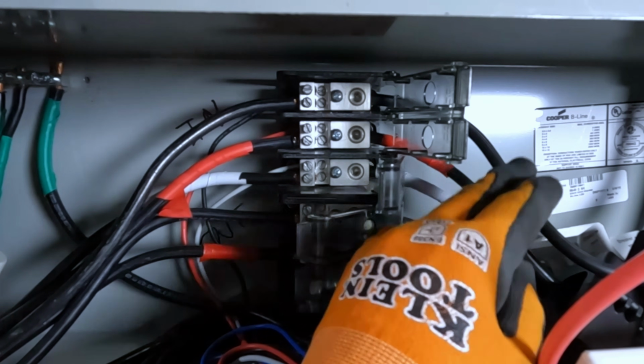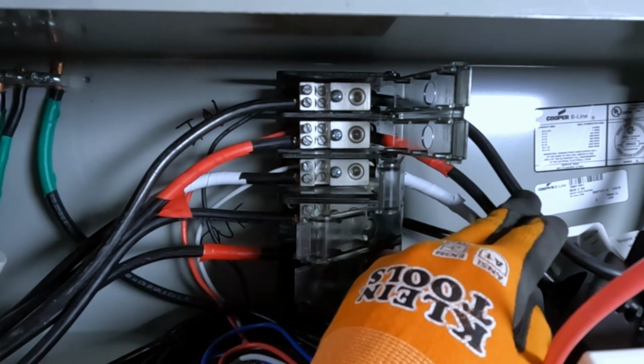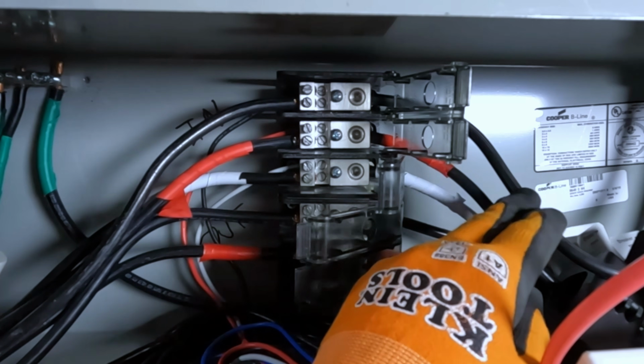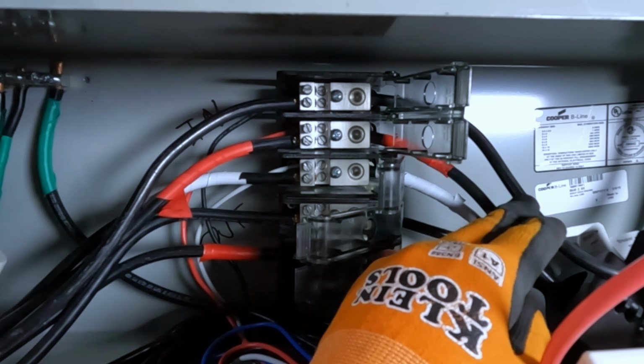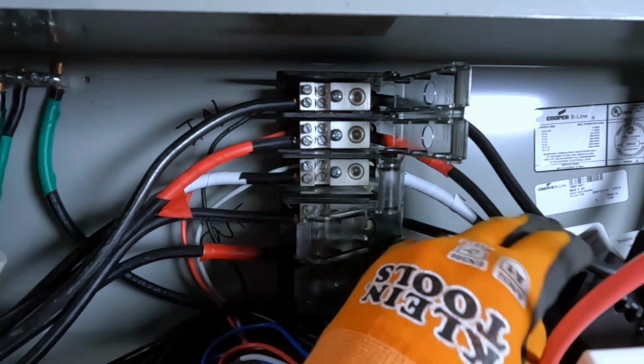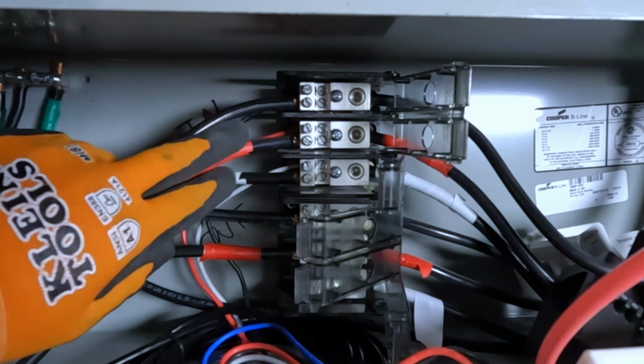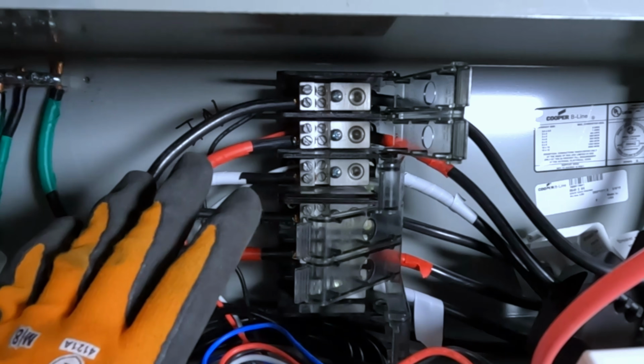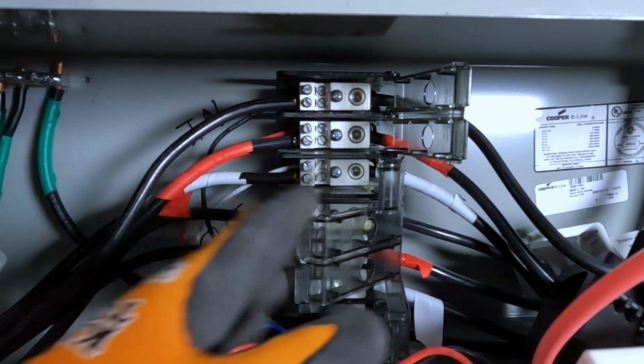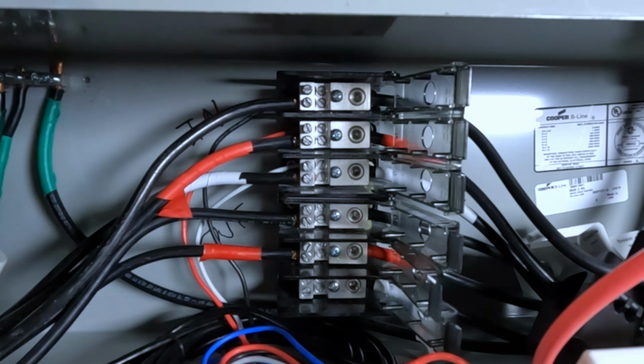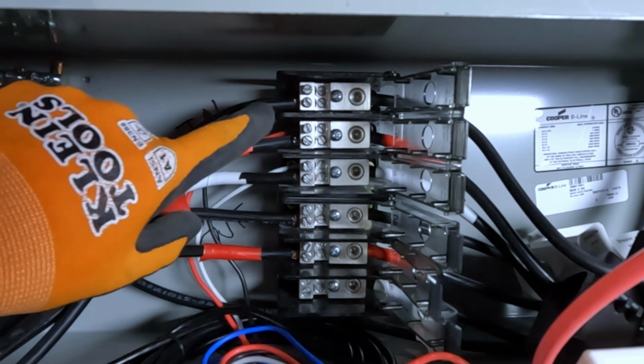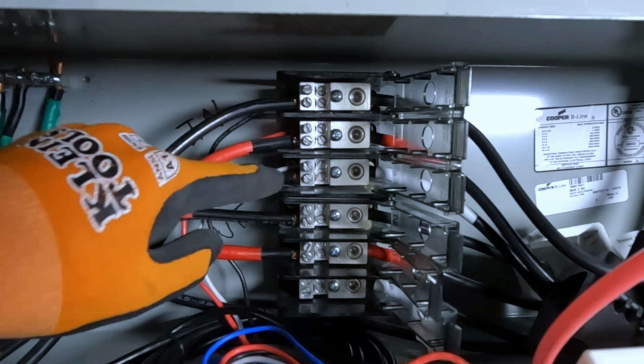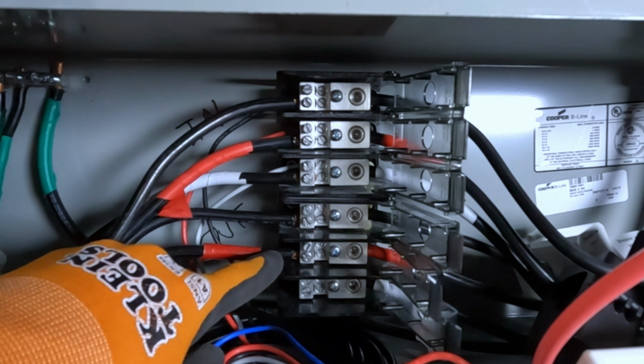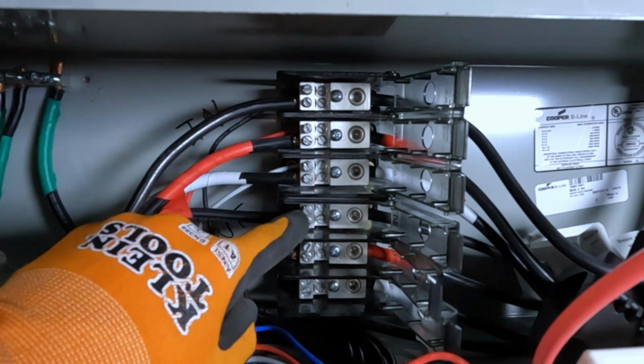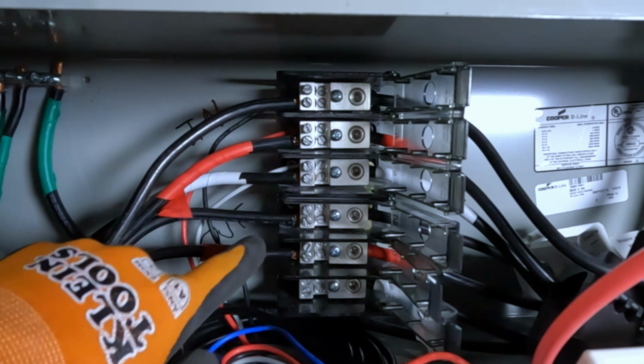Yes, these are not larger gauge wires than 2 combined 4 gauge wires would be able to handle. And again, these aren't even 2 gauge, they are 4 gauge. But I know my loads right now, it is configured for my current loads. So with that disclaimer out of the way, I actually wired these so that the bottom terminal is always going to be the closest inverter. The top terminal will be the furthest away.